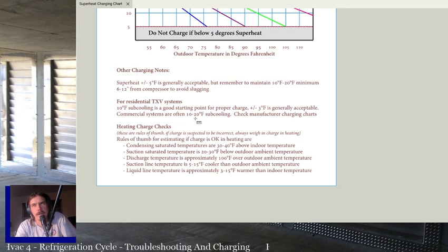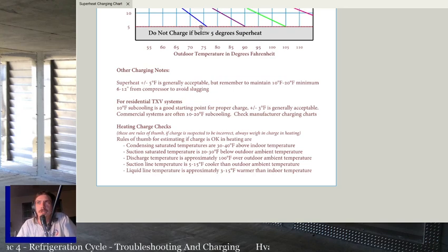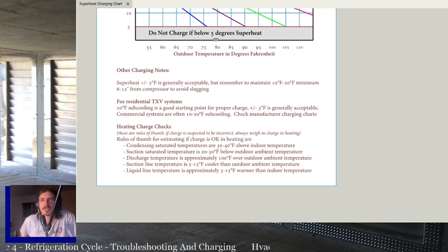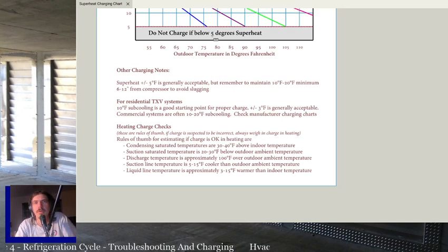So never add charge. You see the line right here, right? Do not charge if below 5 degrees superheat. If you see less than 5 degrees superheat, it might be normal. Okay, you can see these lines start to dip down here at certain temps. There will be times with a fixed orifice that you're kind of low on superheat, and there's not a whole lot you can do about it. That's one of the downsides to a fixed orifice. But if you're below 5 degrees superheat, don't add any charge. There's no reason to charge it until you can get slightly more normal conditions and see where your superheat should be.